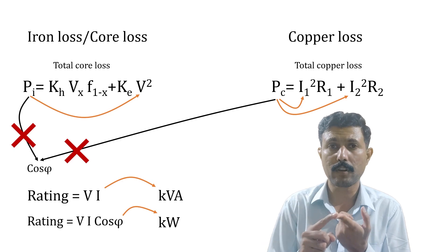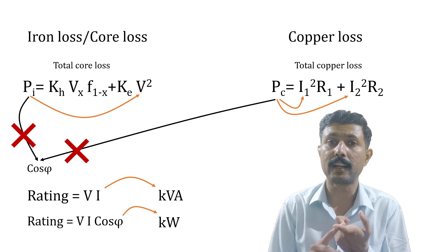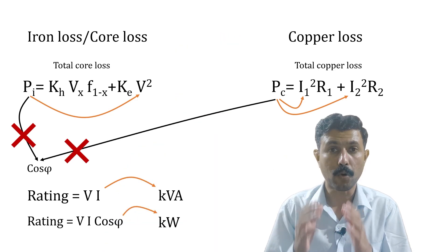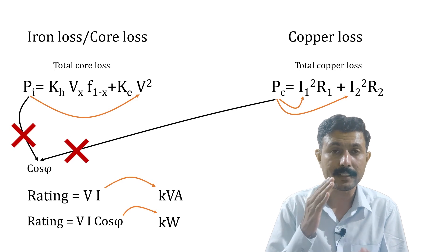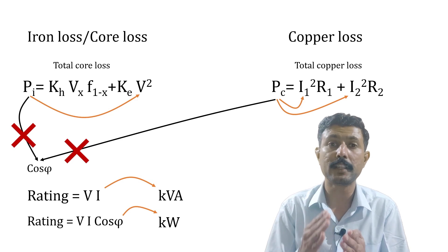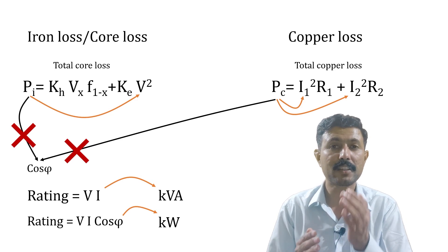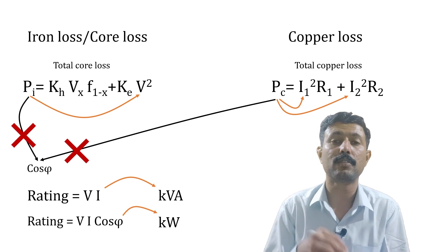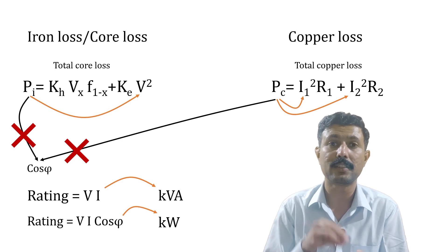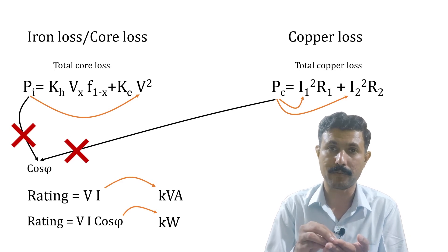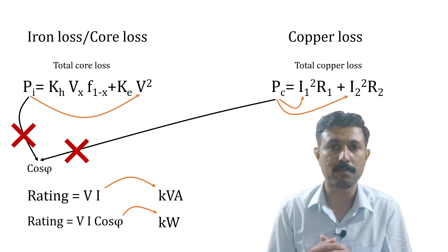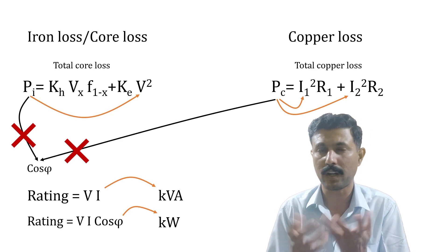This is also true for a motor — copper loss depends on current and iron loss depends on voltage. But a motor is rated in kilowatt. Why? Because a motor actually consumes power, so in addition to these losses we must consider the power consumed by the motor, which depends on power factor. Therefore, we need voltage, current, and power factor together, and that combination gives us kilowatt. That is why motor power rating is in kilowatt, watt, or megawatt.